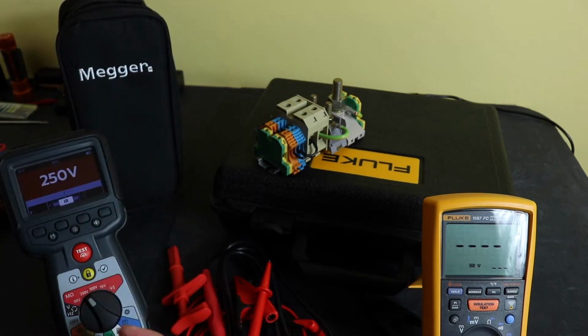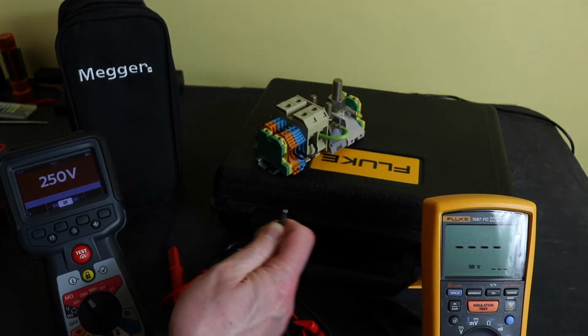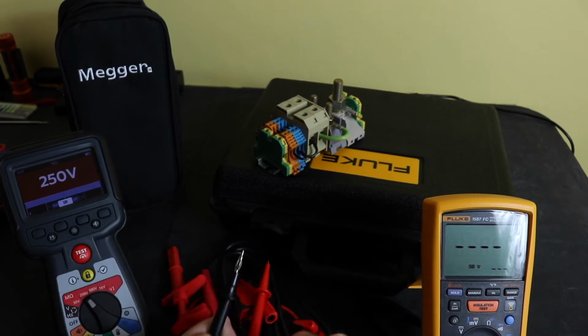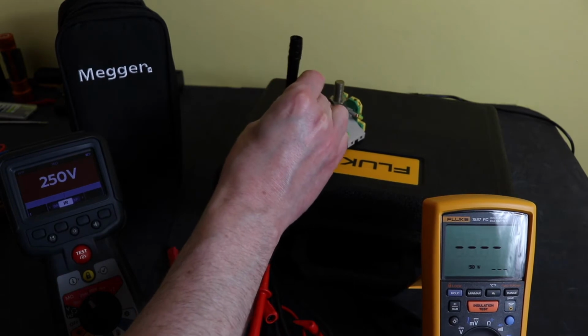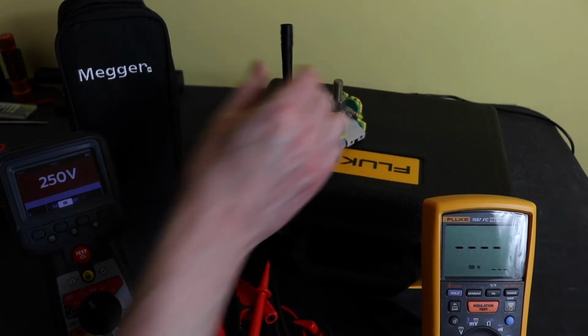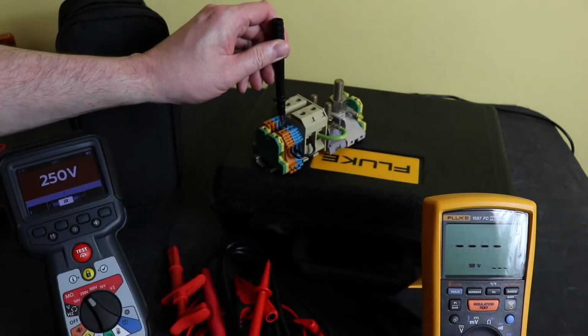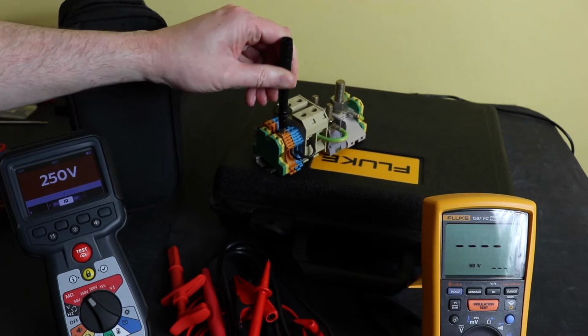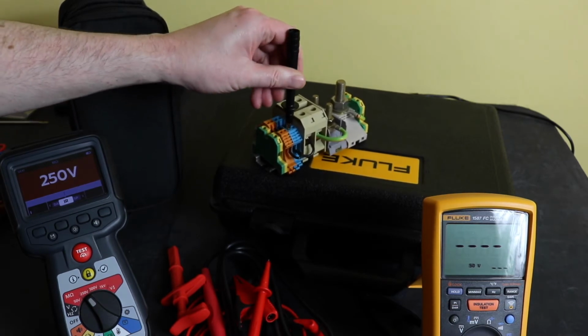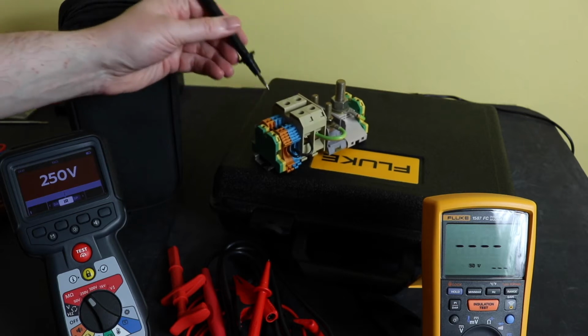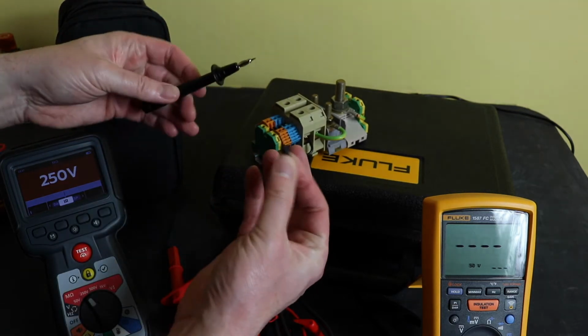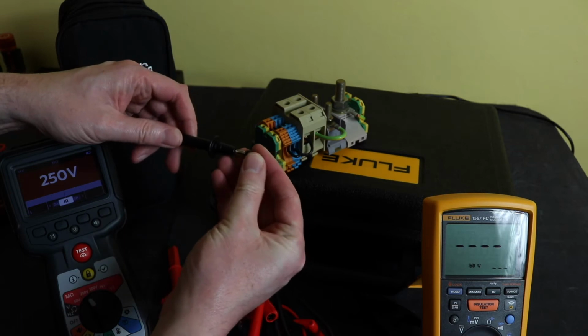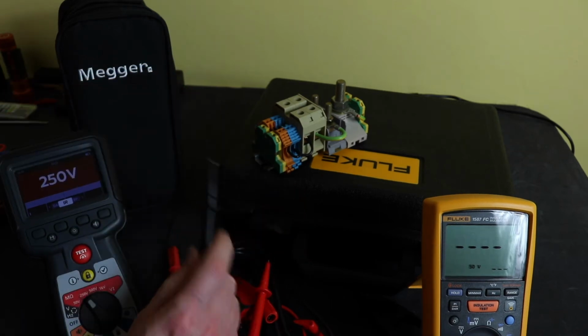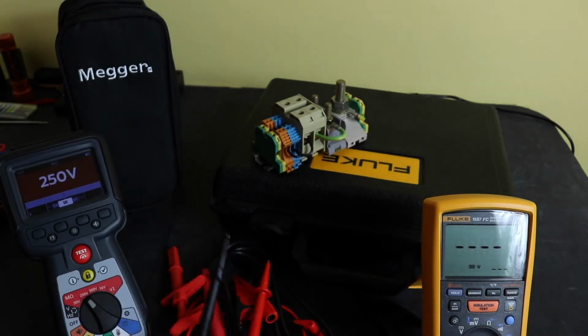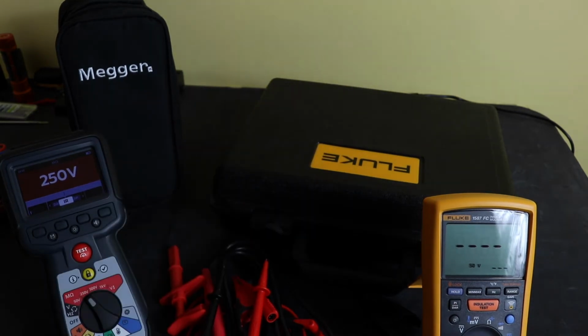You can, obviously, with this probe style, take off the cap, and you've got a standard 4mm adapter there on the end, and there you can just get in there with that one. That's the wrong way around, isn't it? I can feel it just making contact there. And you can get in there with those. But obviously, for my country, for the GS38 protection, you're not really supposed to remove that cap when you're working on live, when you're measuring live voltages. So that's the probes.